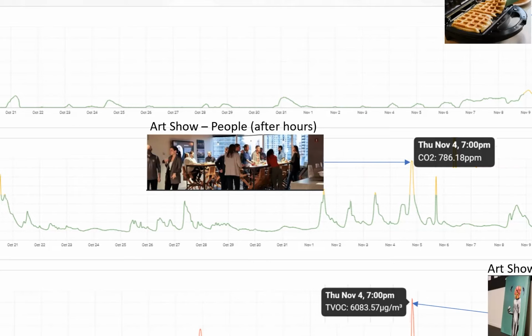But if we look back to the left, there was an art show after hours that week. At 7 p.m. the CO2 levels had spiked up to 786—not horrible, but not high performing. That was with much less people, but we had forgotten to ask for after-hours air, and the building shuts off the HVAC at 6 p.m. If you've ever hung around the office late and heard those ducts contract and the air go off, that's because your lease says 6 through 6.